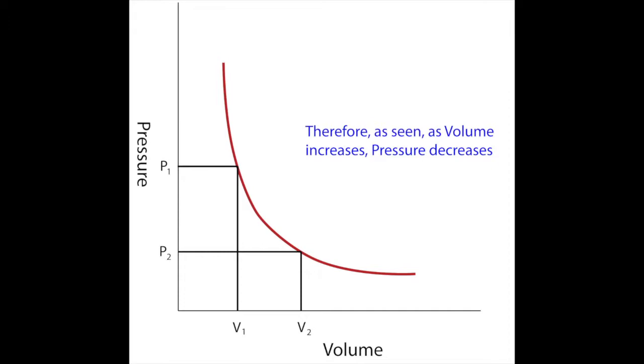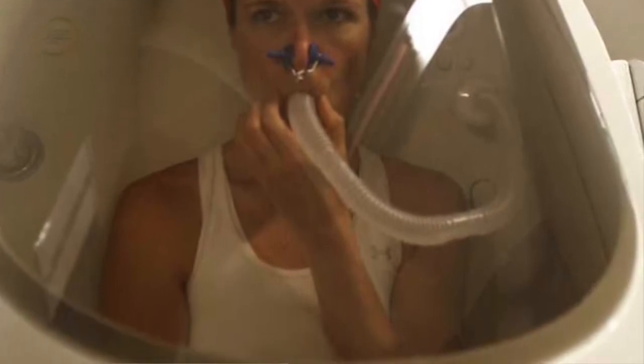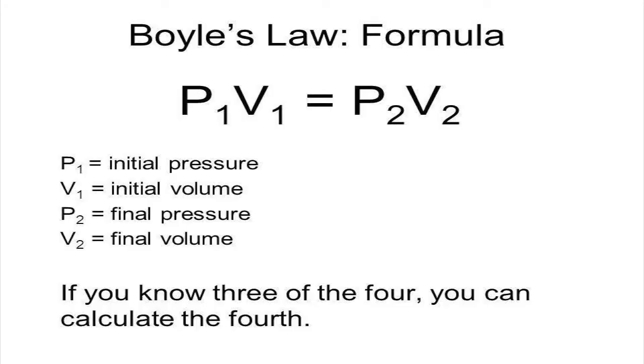To compensate for pressure changes due to breathing and air volume in the lungs that might interfere with measurements, the subject breathes normally into a breathing tube. The Bod Pod can either directly measure lung volume based on relaxed tidal breathing, use standard prediction equations based on gender, age, and height, or use a previously determined lung volume. Once the lung volume of the subject is determined, the system uses Boyle's Law to calculate the volume of the subject as a whole.